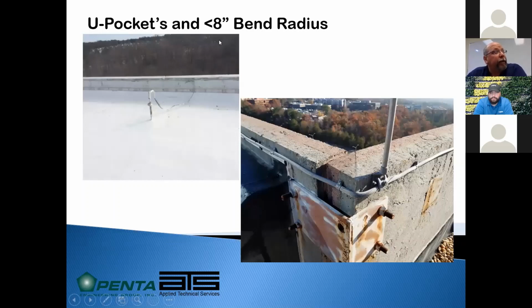Now, I mentioned the bend radius issue and U-pockets. So NFPA and UL both state that lightning protection conductor needs to maintain a horizontal or downward path. It does not like going uphill. It can go down as fast as we can take it down, but they do not want the conductor to rise at greater than a 1/4 slope. So 1 inch for every 4 inches horizontally, or 1 foot for every 4 feet horizontally.